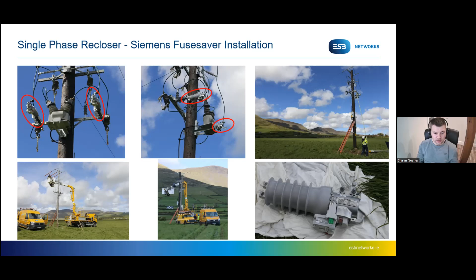But we had one example east of Dingle, where we had one of these devices with 76 customers connected downstream, circled there in red. And what actually happened was there was a lightning storm, and on the diagram in the bottom right, you'll see all the circled lightning strikes, taken from the internet. And we also saw damage reported by customers at a point on the network. And from the parameters that were sent into our SCADA system, we were able to see the device operate. So it picked up the fault, it opened and disconnected the fault, and then the fault had cleared, the recloser reclosed, and the customers were brought back onto supply. Now, in terms of customer minutes lost, that was a significant saving for ESB Networks, but more importantly for all the customers, most of them would hardly have really noticed that particular outage.